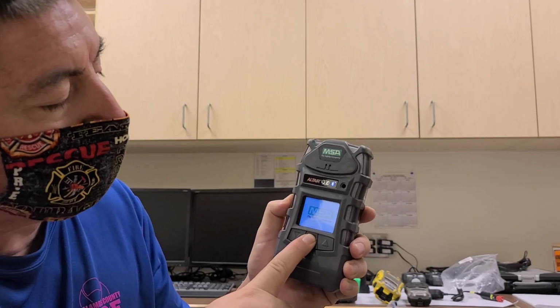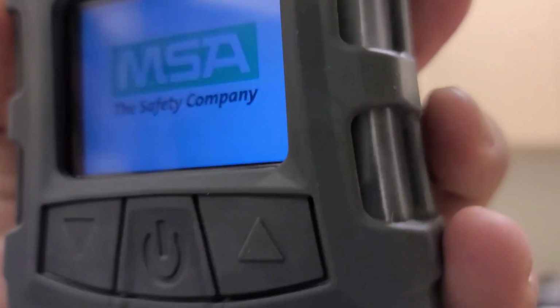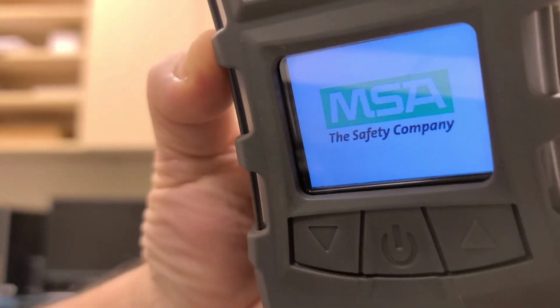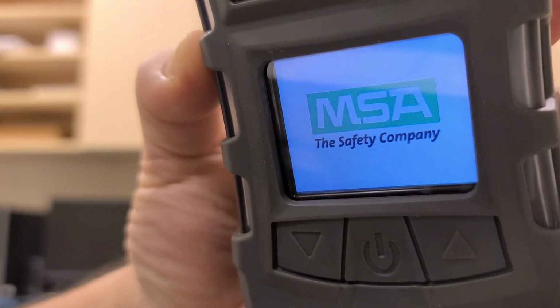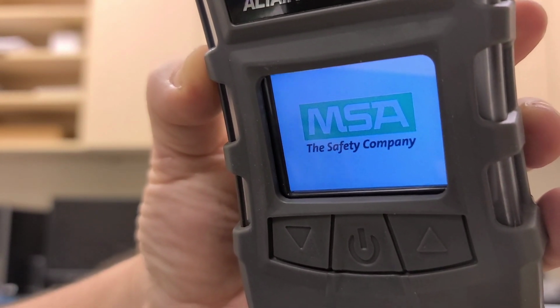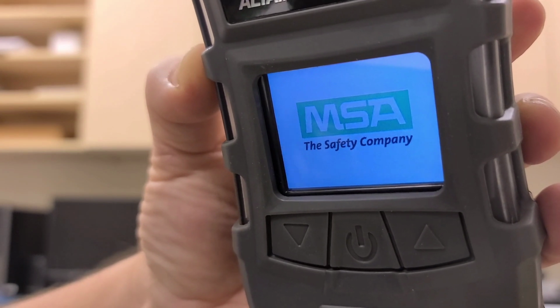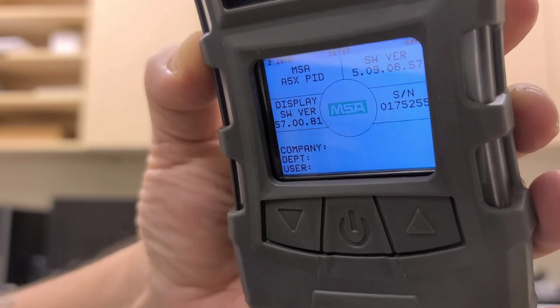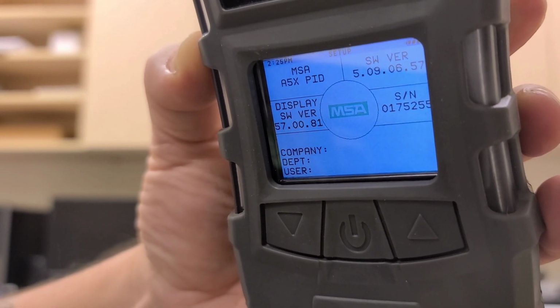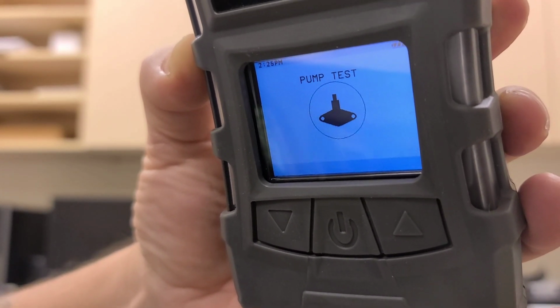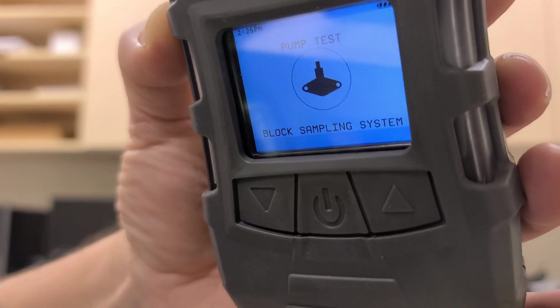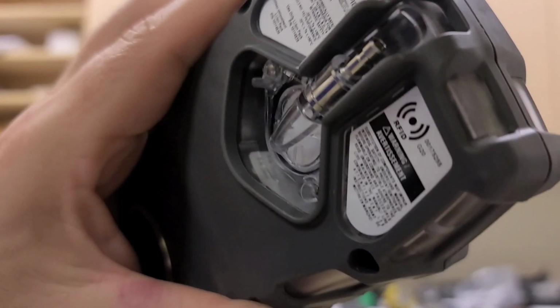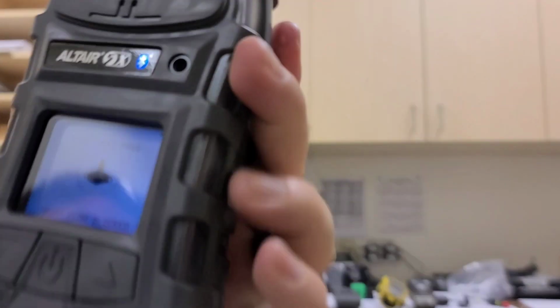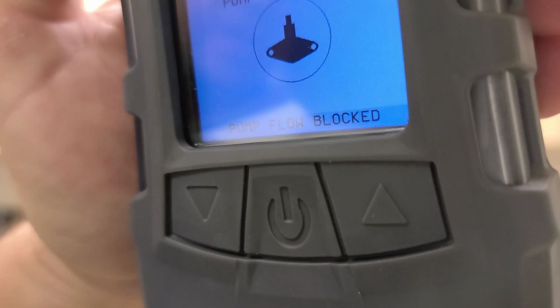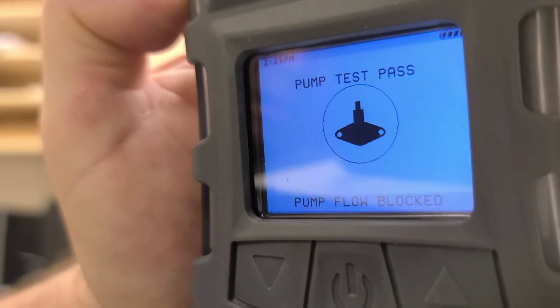So here's what it looks like when you turn it on. Hold the button down for 4 seconds. Same when you want to shut it off. It's going to have a turn-on cycle time where it's starting to warm the sensors up. It's going through all the menu options, all of its software, and so forth. It's going to display the serial number and so forth. You don't need to be worried with that. This is the section where you have to do a pump stall test. It says please block sampling system on the back. It's going to be your pump right here. This is the pump and the inlet. You just block your inlet with your finger till it's done. It's going to say pump flow blocked, pump test pass, and you're good to go.